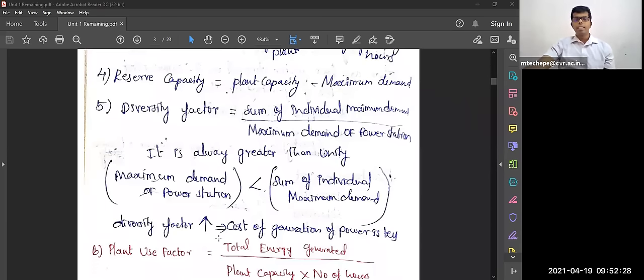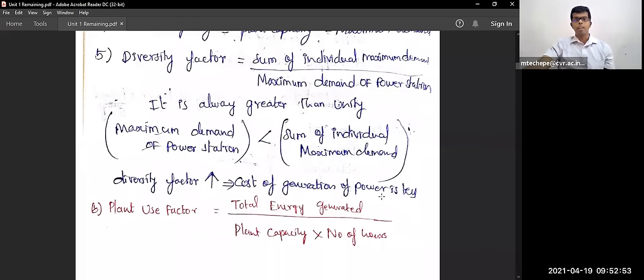The maximum demand of the power station will always be less than the sum of individual maximum demands — that is why diversity factor is always greater than one. If diversity factor increases, the cost of generating power decreases.